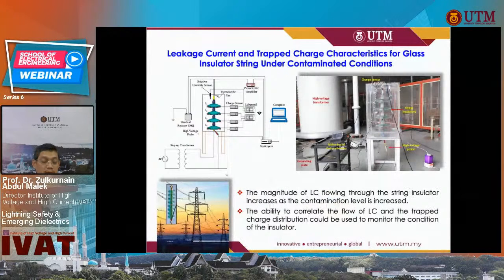Another diagnostic that we can do is to detect the leakage current on the string insulators. These are on the overhead transmission line where we hang our phase conductors. To detect PD may be difficult, but it is possible to detect leakage current that flows inside the insulators. So if we can do this technique, it is very useful to pre-diagnose our insulators before they fail, and therefore cause supply interruption, for example. So we developed this tester in the lab and measure leakage current and correlate it with the trapped charge.